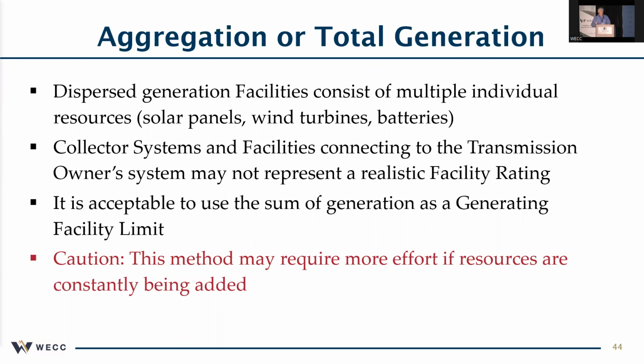So we have seen collector systems that cannot handle the full output of the turbines. In that case, those collector systems, even if they're not BES, can indicate a limitation on that facility. In some cases, the collector systems are built robustly enough to take full generation for all the individual turbines there. Then maybe those turbines themselves can be the limiting factor. So what we're allowing is that you can do your facility rating based on your electrical facilities.